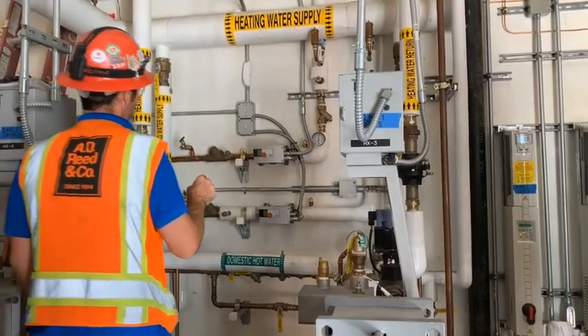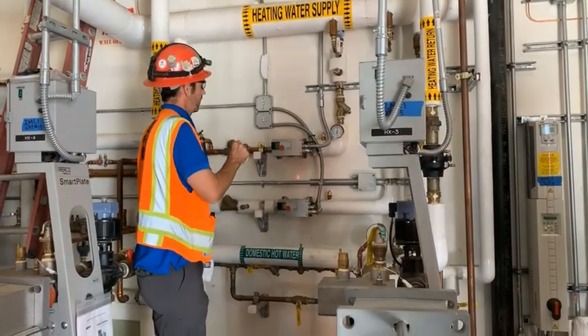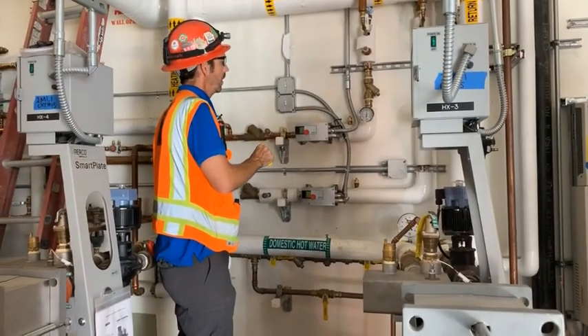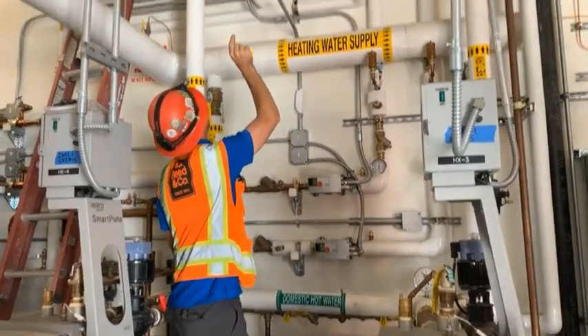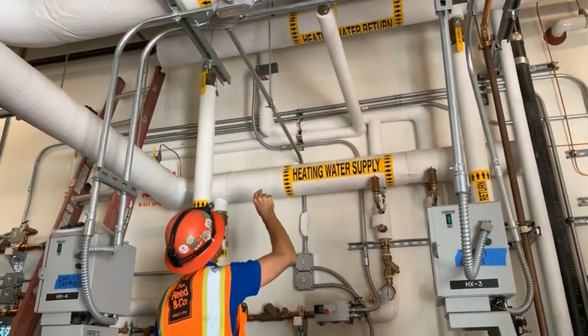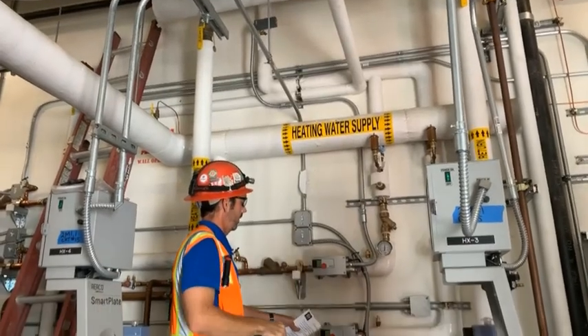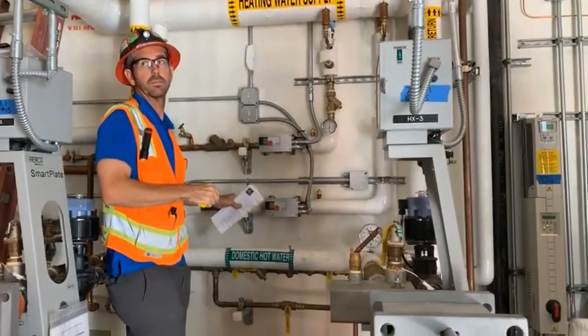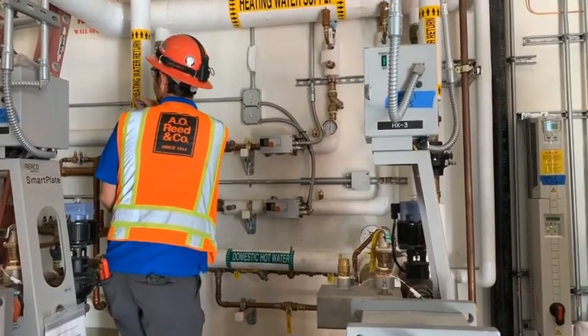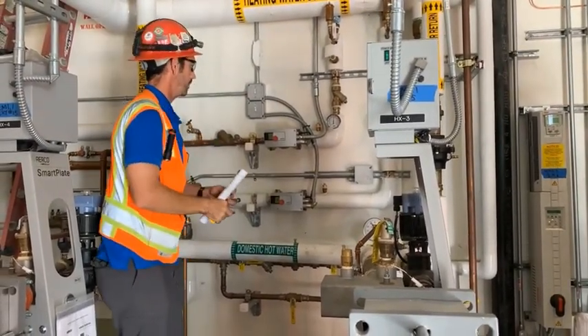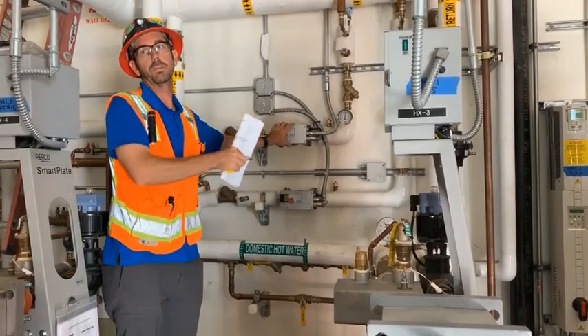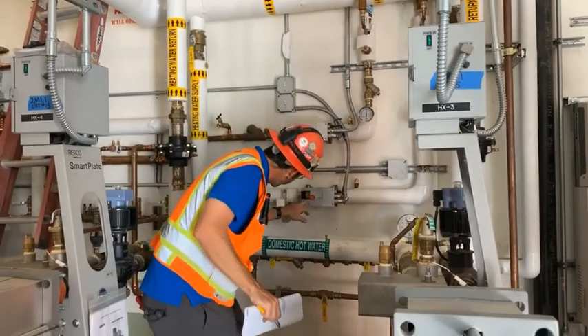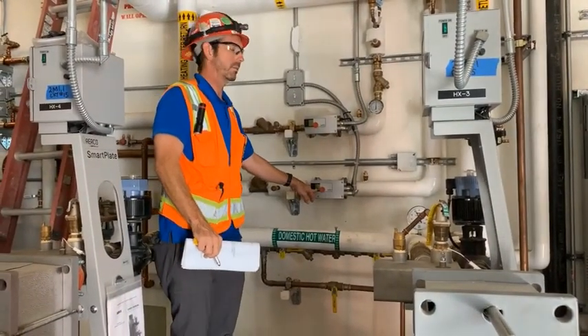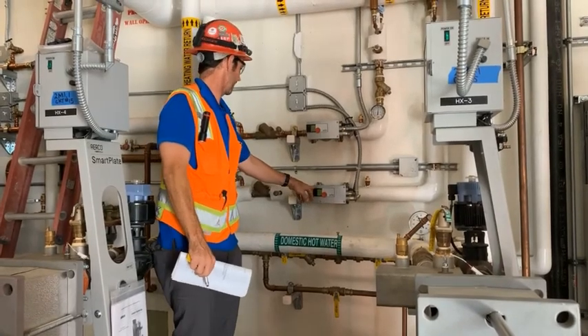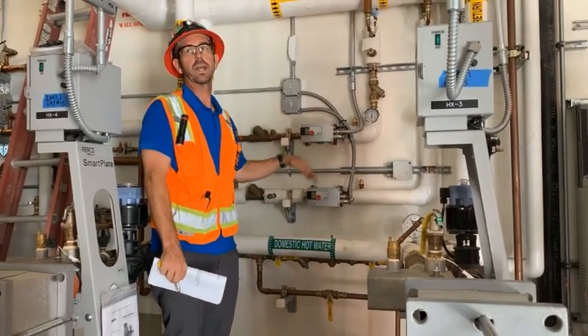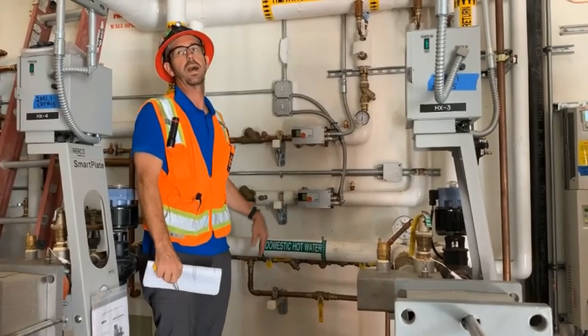So over here, we have circ pumps. These two are your building circ pumps. These are taking the water from the 8th floor down here. Here's your aquastat. It comes down, it splits apart. Remember, these are twin. Twin means that only one will run at a time. Building circ pumps. We have the tank circ pumps on the wall over here. Is that manually set? The switching will be done automatically through the master. This one right here is the master and this one is the follower. The master will decide, I've run for a week, I'm going to let you run for the next week. But again, we'll have training on that tomorrow.